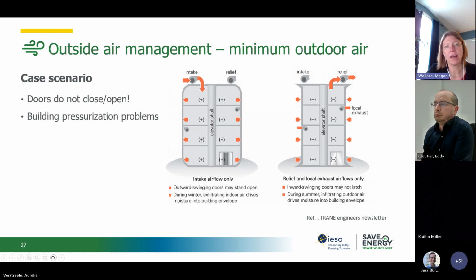Here's a scenario of building pressurization problems. Usually, these happen when your doors won't open or close properly. In cases where we're over-pressurizing the building, where we have too much outdoor air intake, you'll notice that the outward swinging doors will stand open and will be difficult to close. They won't close behind people as they're leaving.